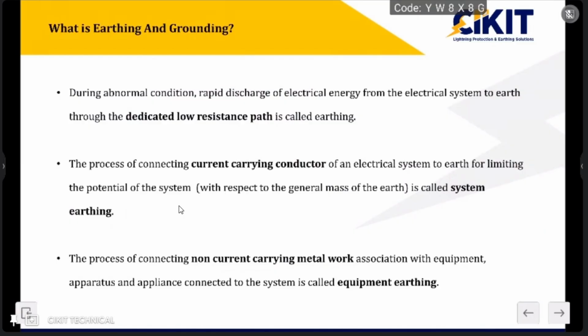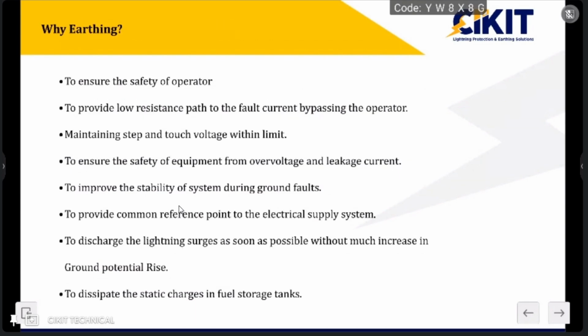A substation contains both system earthing and equipment earthing. Usually the transformers are connected to earth only at the substation area, so system earthing comes into the picture there. Similar to equipment earthing, we cannot choose the sizing randomly for system earthing. The sizing has to be done properly, and based on proper calculations we have to select a suitable size for the earthing of transformer neutrals.